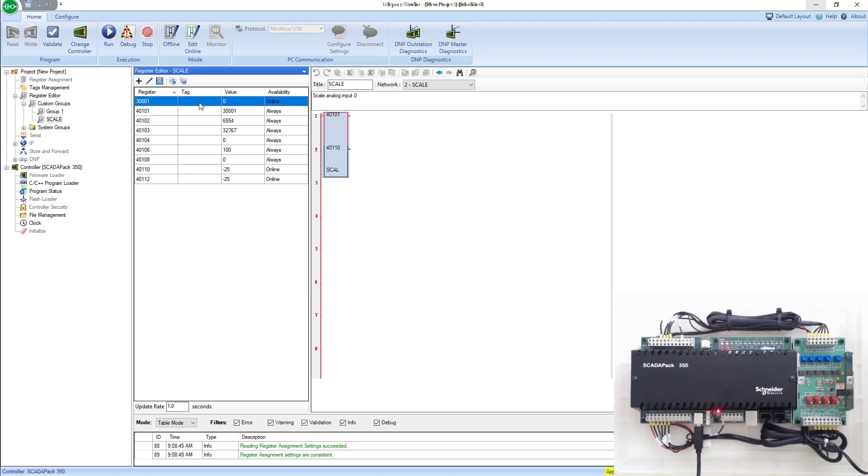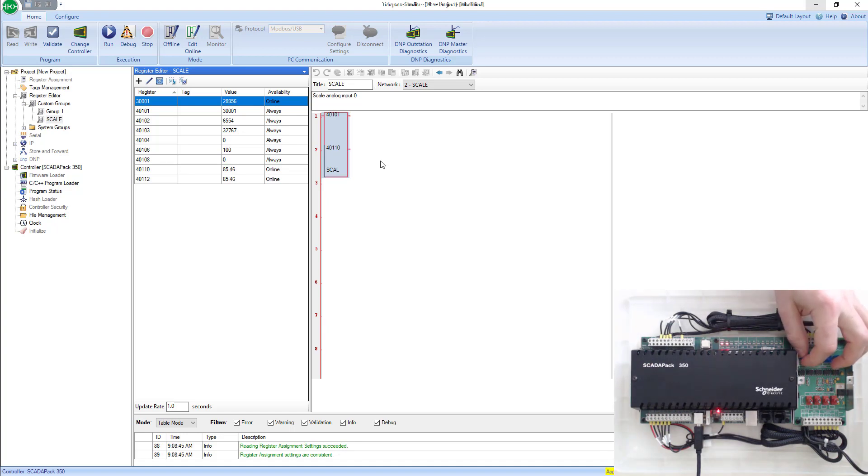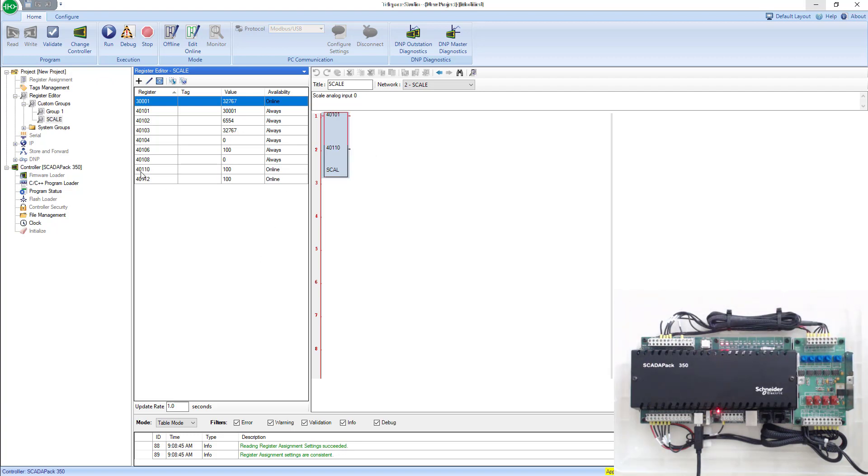Now I can see my 30,001 sitting at zero, so obviously my analog input is at zero. If I crank that up all the way, I get 32767. I see my 40,010 as my full scale is 100.